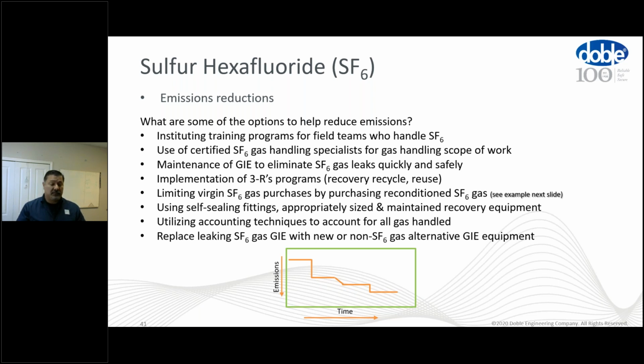Using certified gas handling specialists. Maybe you don't have a big enough team to go out there and do your gas handling. So bringing in teams or organizations that are certified in gas handling and understand the scope of accountability, emission-free recovery, no emissions to the atmosphere while handling is very important. Maintaining your GIE to eliminate SF6 gas leaks quickly and safely. Not having that cylinder strapped to the frame of the GIE with a little positive pressure, getting rid of that concept needs to come into play, and replacing those leaking breakers right away.